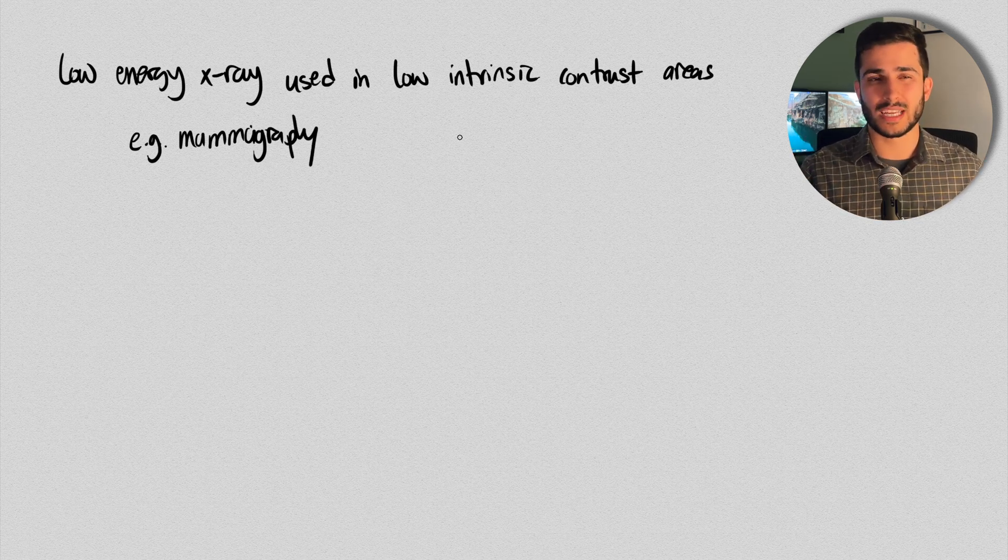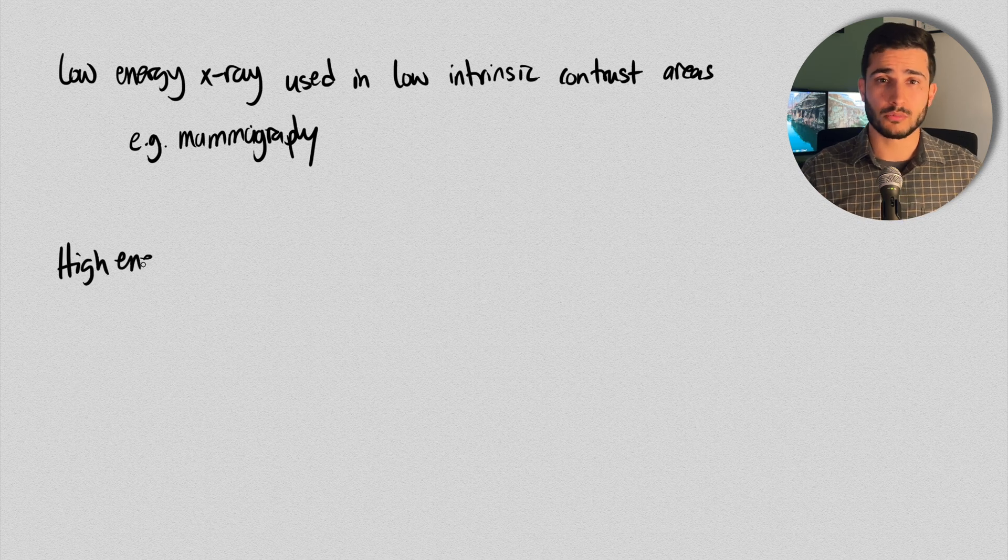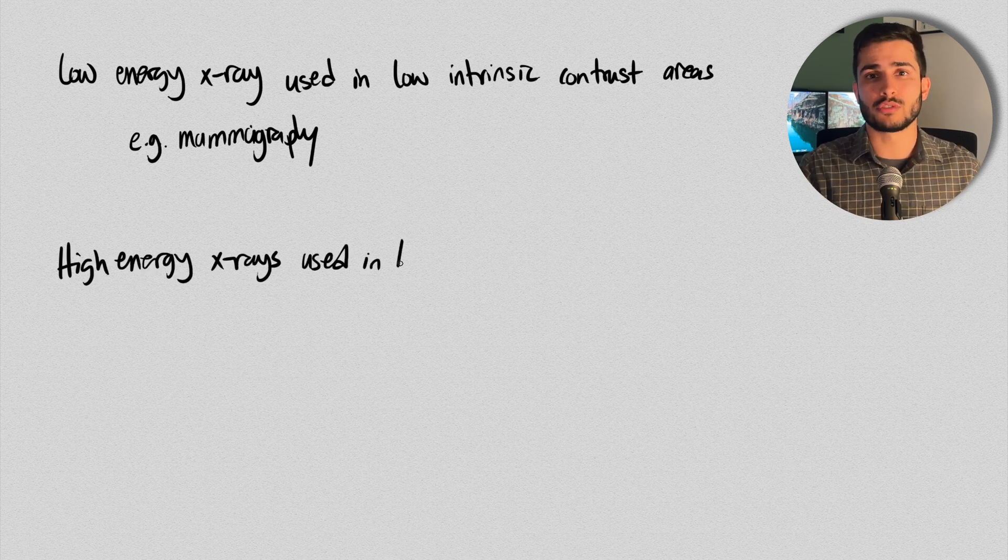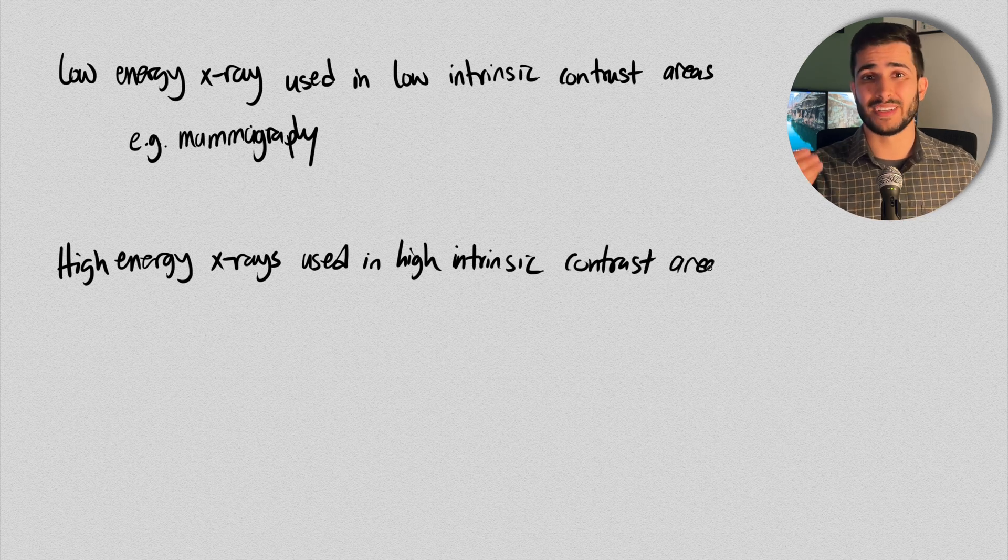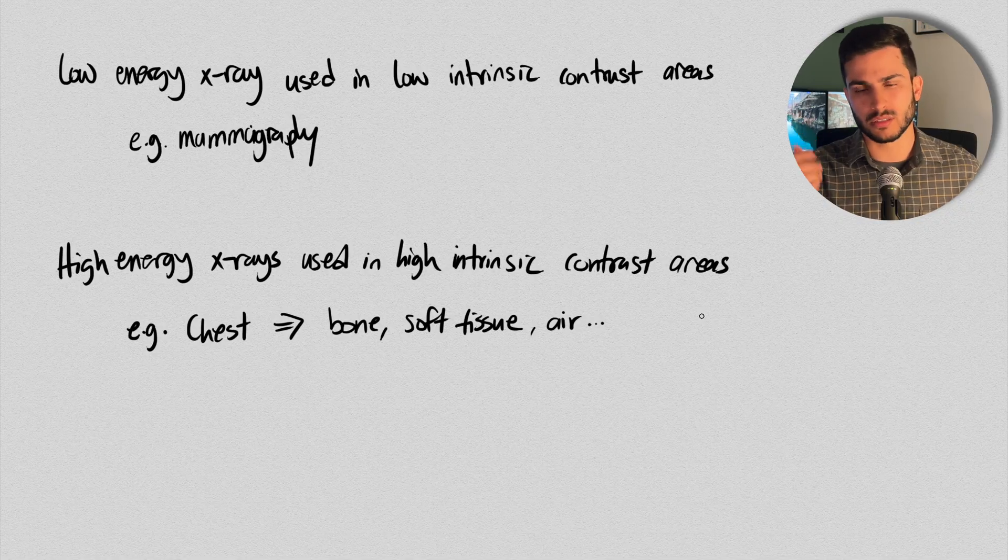As in mammography, they usually use anywhere from about 27 to about 31, 32 kVp, which is definitely on the lower end. And then on the other side of the spectrum, when we're dealing with an area of high intrinsic contrast, such as the chest, where you have bone, soft tissue and air, then that's where you want to use your higher energy X-rays, which when you think about your chest exposures, it ranges anywhere from about 100 to 125 kVp, depending on the machine.